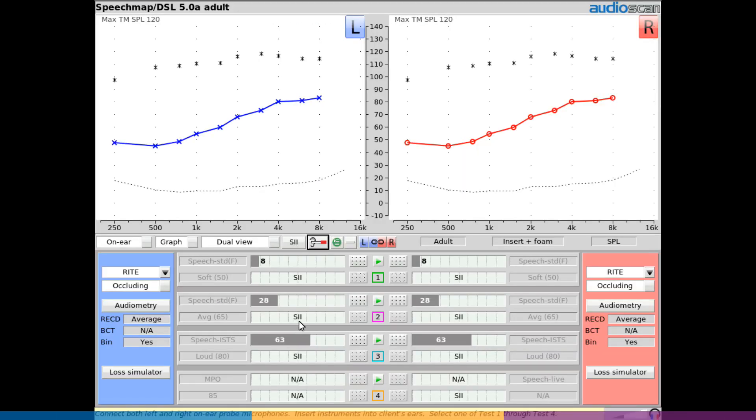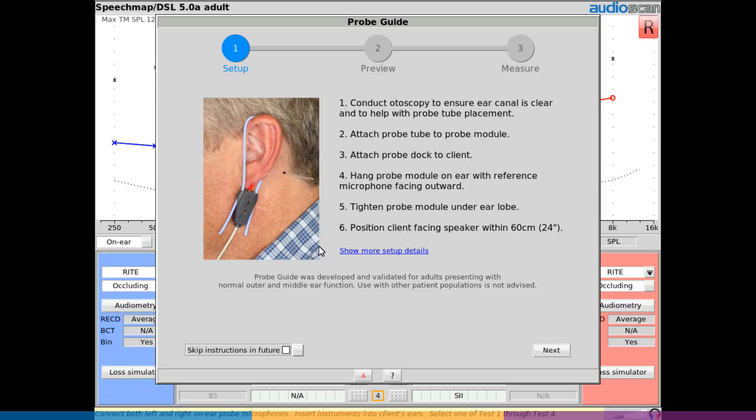ProbeGuide can be opened by selecting the probe guide button from within any test screen which includes on-ear measurements. Upon launching the tool, the Setup tab provides guidance on preparing the client and the equipment for real ear measurement.